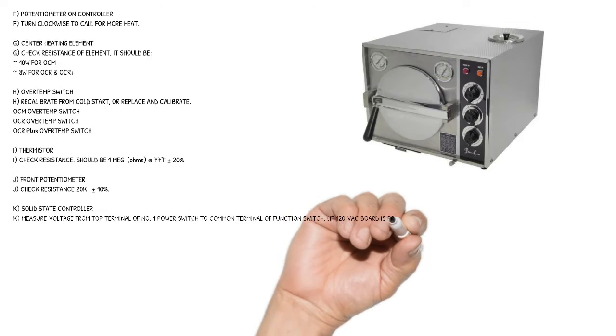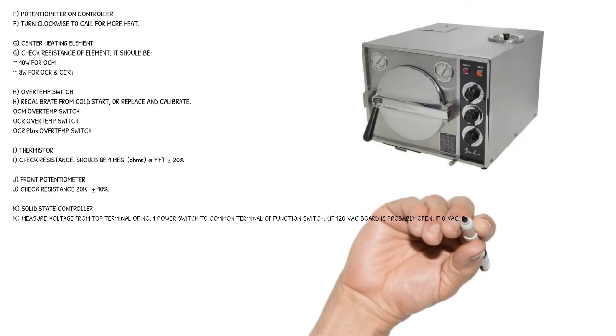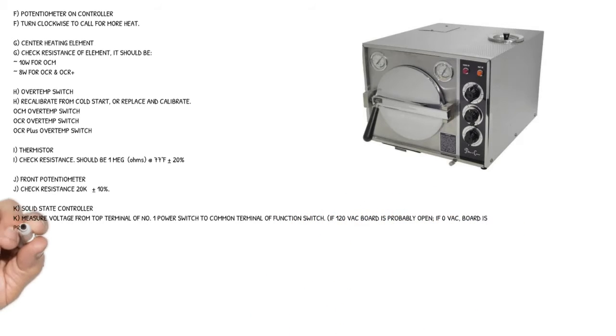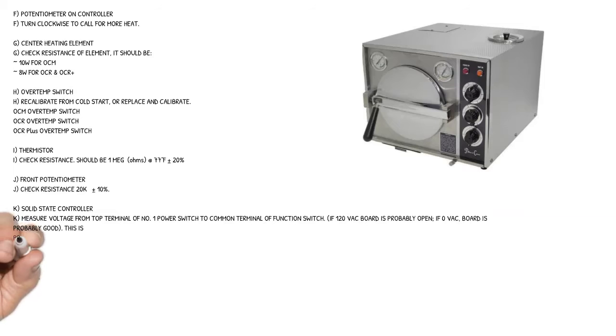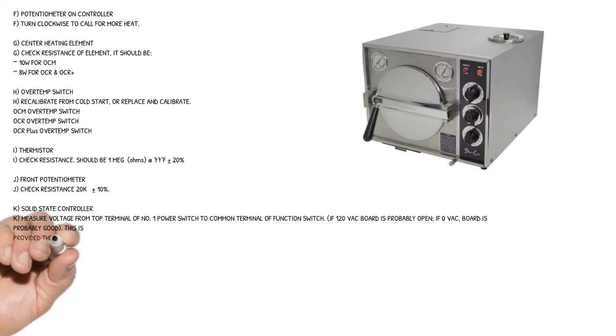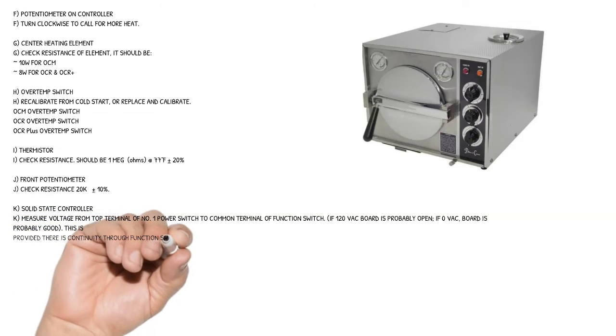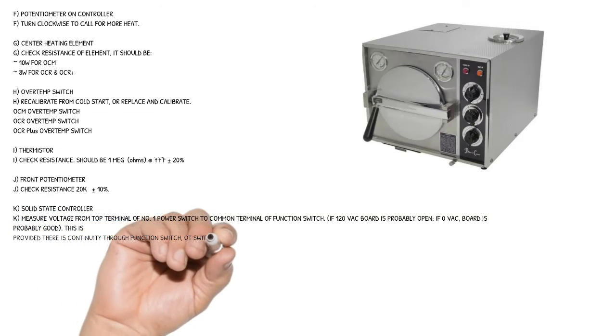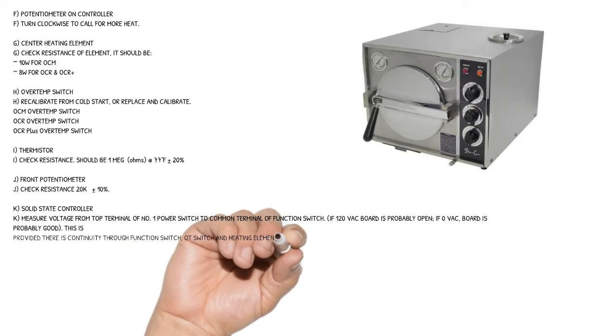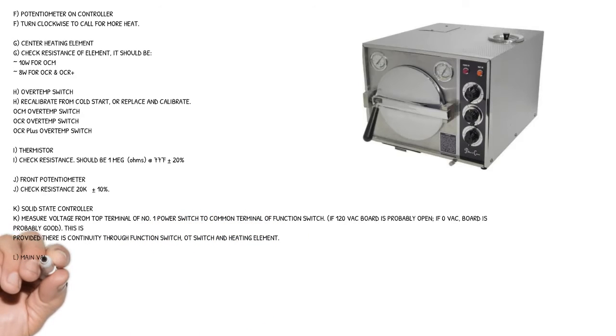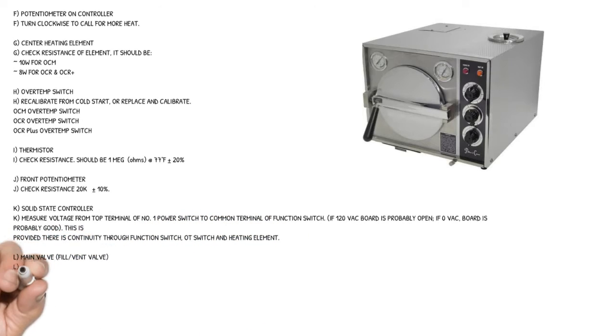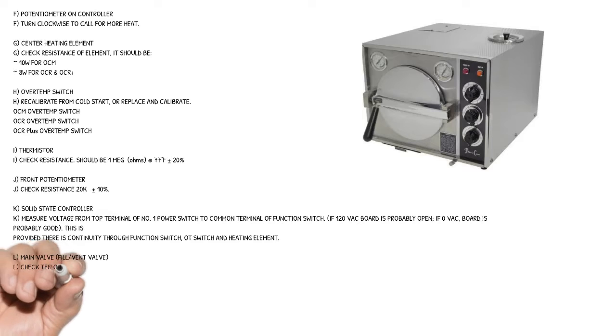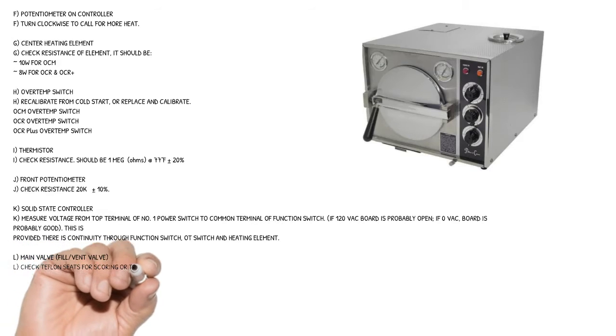Cause K: solid state controller. Measure voltage from top terminal of number 1 power switch to common terminal of function switch. If 120 VAC board is probably open, if 0 VAC board is probably good. This is provided there is continuity through function switch, OT switch and heating element.